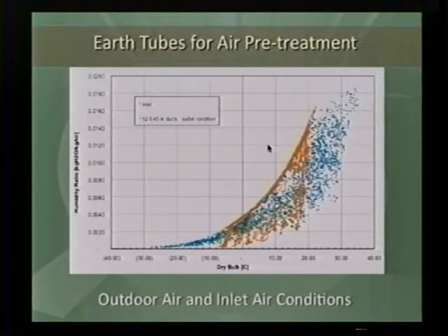And so you can see the 100% line on the psychrometric chart running down the edge of this curve. And you can also see that the yellow dots, which are the outlet from the earth tube, are running all along that saturation line. That is, we're getting condensation in the earth tube. And you can see up at the top of the chart that condensation is actually doing some dehumidifying as well as cooling the air. So there's a lot of cooling that's going on, but not a lot of heating.